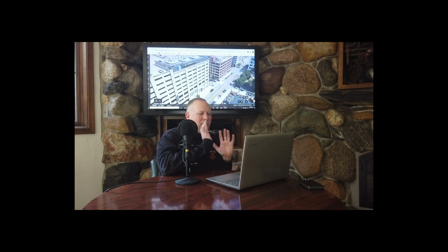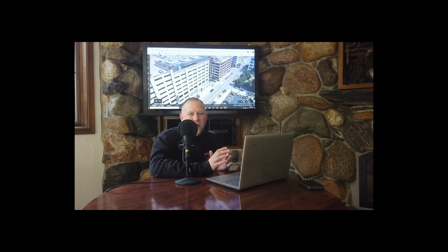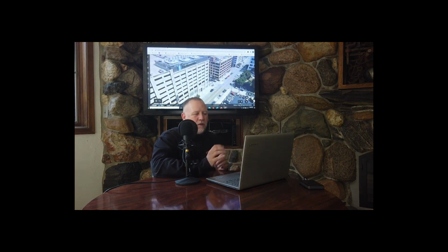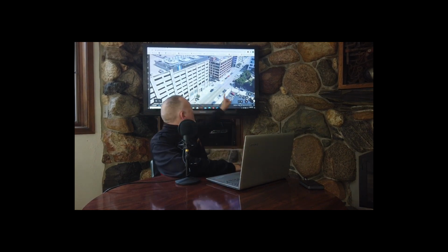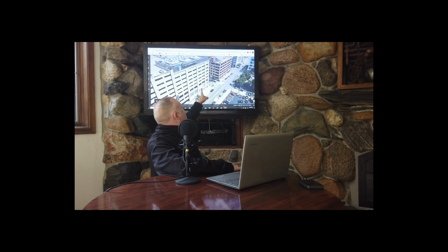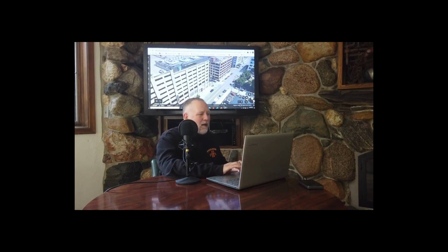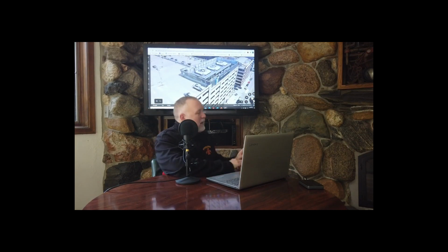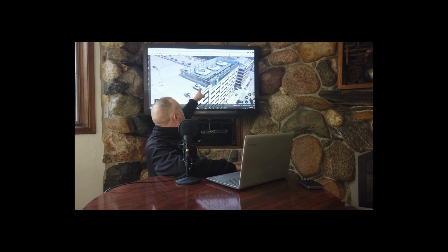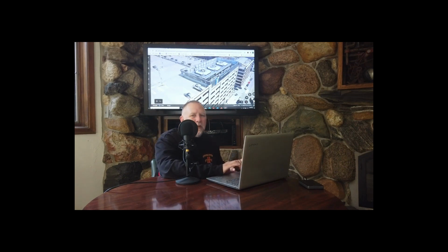Now, why this is pretty awesome from the perspective of a cooling plant is they put their chillers and their whole cooling plant away from their office space. They have the expensive space, which is the office space, and then they have the parking ramp. The parking ramp is obviously much cheaper, dollars per square foot. The maintenance for these are easy. This is a big overhead door. I can just drive right in with a truck. The cooling towers need maintenance. I can just drive a service truck up to beside them and just go right to them there. Makes this really, really easy.